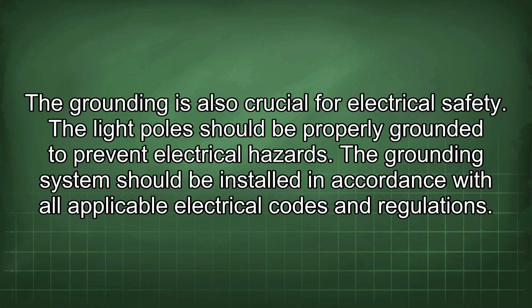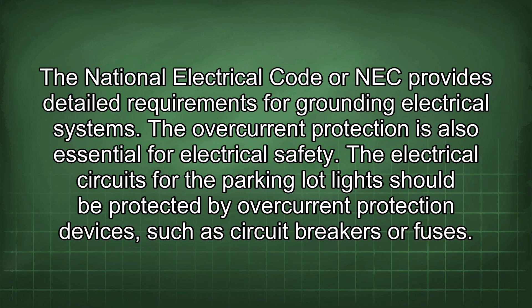The overcurrent protection is also essential for electrical safety. The electrical circuits for the parking lot light should be protected by overcurrent protection devices, such as circuit breakers or fuses. These devices will protect the wiring from damage in the event of a short circuit or overload. The type and size of the overcurrent protection devices should be selected in accordance with the NEC.